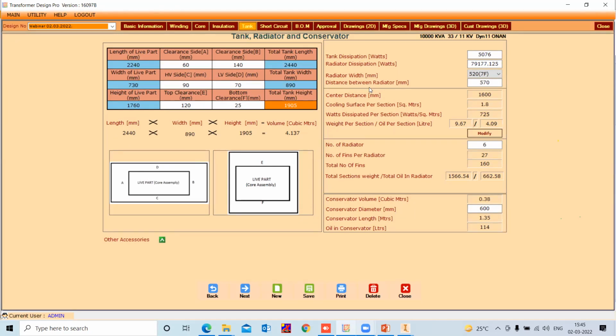Now let's see the right hand side part. There is tank dissipation and radiator width. Multiple standard options are available here, like from 226 mm to 520 mm, and based on that, your number of fins will change accordingly to whatever width you have selected. So if you have any limitations for dimensions, you can rearrange using this functionality and fix the dimensions as per your requirement. Thereafter, the center distance, then the number of radiators. This value is also available to edit, and based on that, your total number of fins per radiator will change automatically.